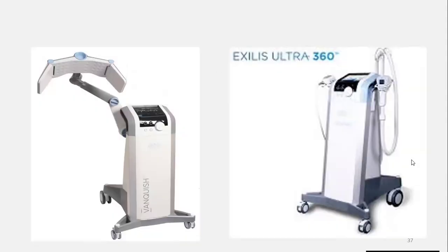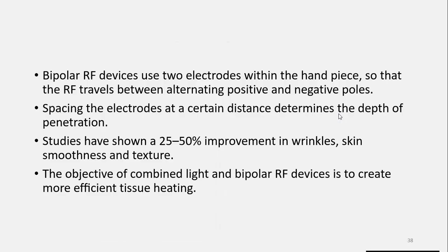These are two monopolar radiofrequency devices by BTL. This is Vanquish ME and this is Exilis 360. Bipolar radiofrequency devices use two electrodes within the handpiece so that the radiofrequency wave travels between alternating positive and negative poles. Spacing the electrodes at a certain distance determines the depth of penetration.